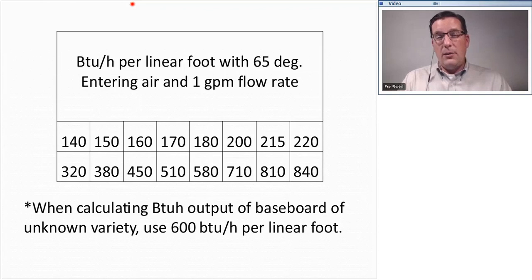But here is the way baseboards are supposed to be sized. They're meant to be a certain amount of BTU output per linear foot. So the longer the baseboard is, the more BTU it puts out. The higher the water temperature is, the more BTU it puts out. This is a chart from, I think, a Slant/Fin baseboard, and it's pretty standard. Almost all 3/4 inch residential baseboard has an output very similar to this.